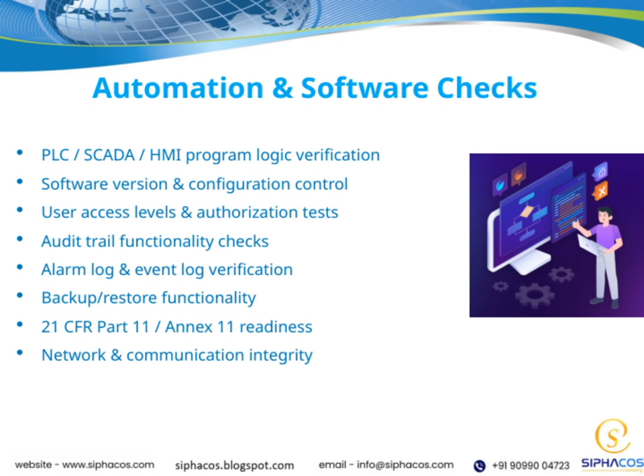We also verify alarm logs and event logs to confirm that critical alerts are recorded accurately and can be reviewed when needed. Backup and restore functionality checks are performed to guarantee data integrity and system recovery capabilities in case of failures. Regarding compliance, we ensure our system is ready for 21 CFR Part 11 and Annex 11, which set the standards for electronic records and signatures, especially in regulated environments. Network and communication integrity checks confirm that data transmission remains secure and reliable across all connected devices.